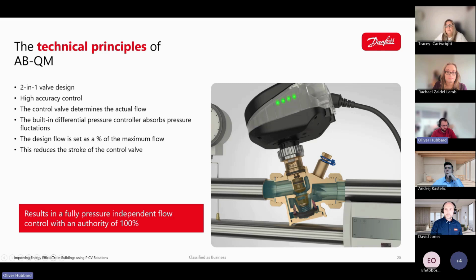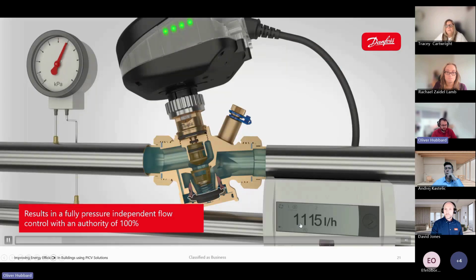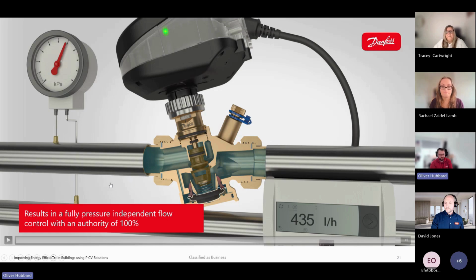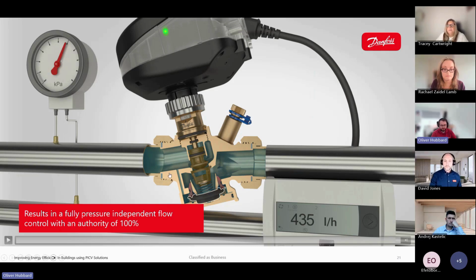As the system pressure rises or falls due to load changes, valves opening and closing or pump modulation, the differential pressure controller adjusts automatically to maintain stable conditions across the control valve. Because of this, the design flow is set as a percentage of the valve's maximum capacity. So if the valve will do 20,000 litres an hour, and you need it to do 10,000, you'd set it to 50%.